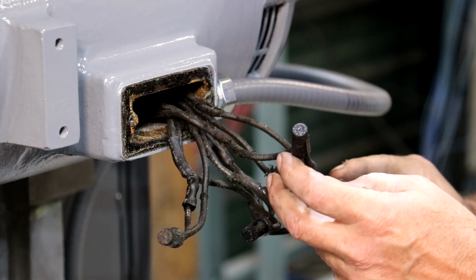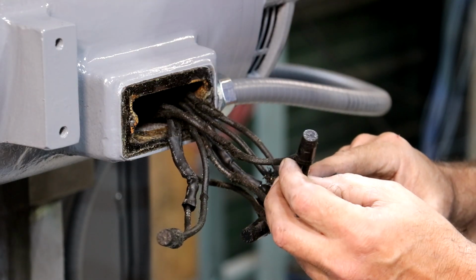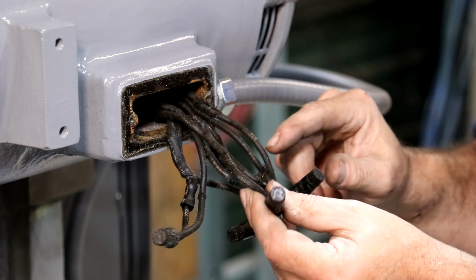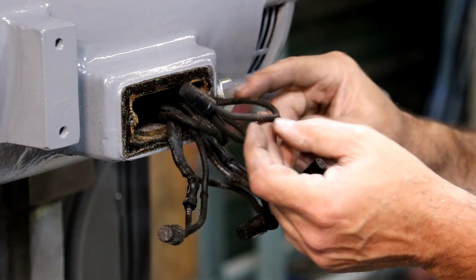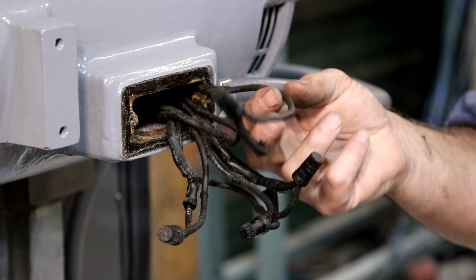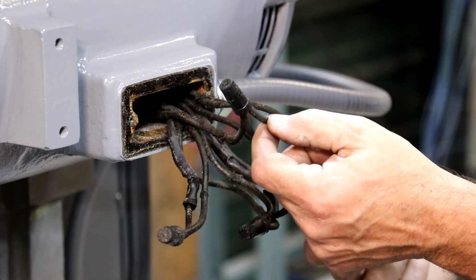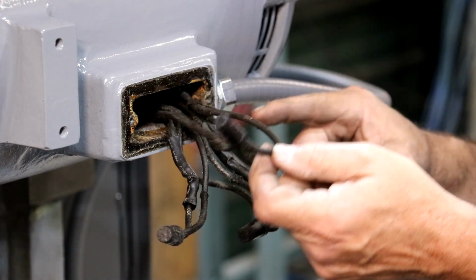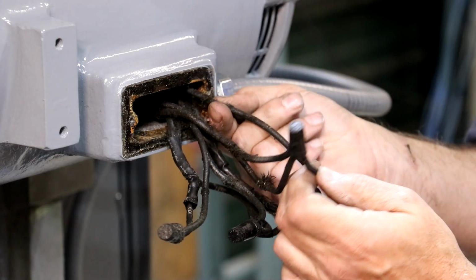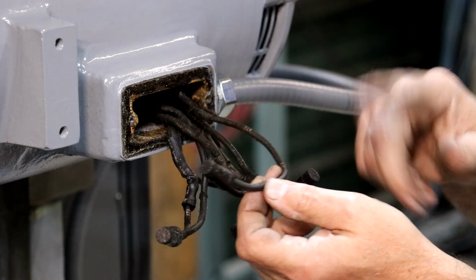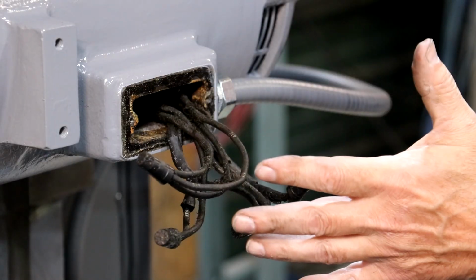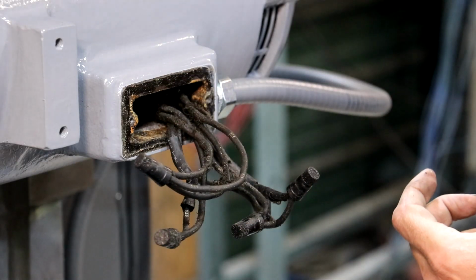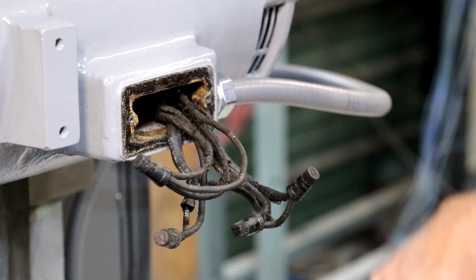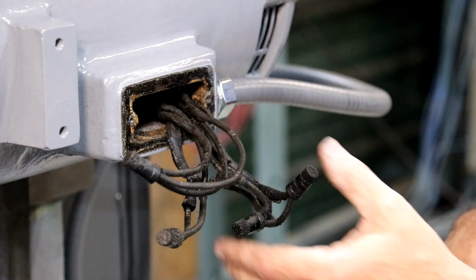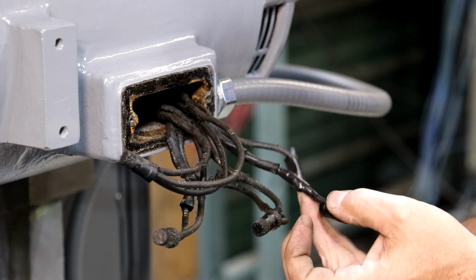All these wires are also numbered 1 through 9. This is number 4, that's number 6, this is number 5. It's hard to read them, but I've got it. I've got some little heat shrink labels I'll put on here as well to renumber each wire as we go, so we have good insulation and the right number on there. Once I do that, I'll tie them together as needed. There's a diagram on the back side of the motor showing how they need to be wired together for the voltage we're giving it.